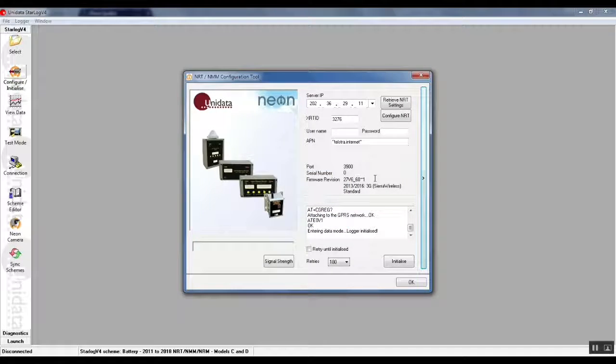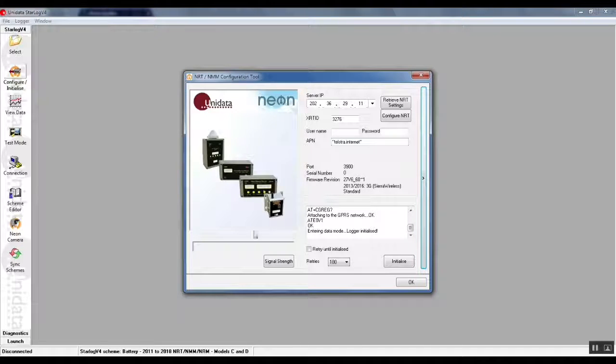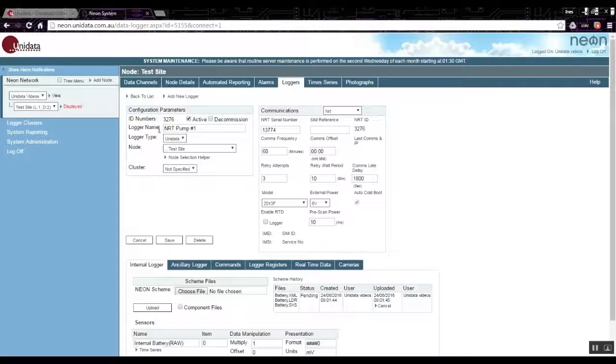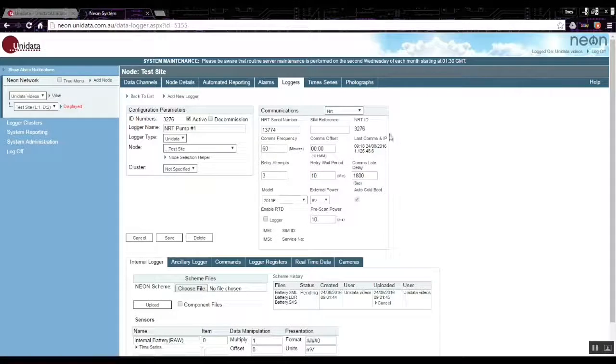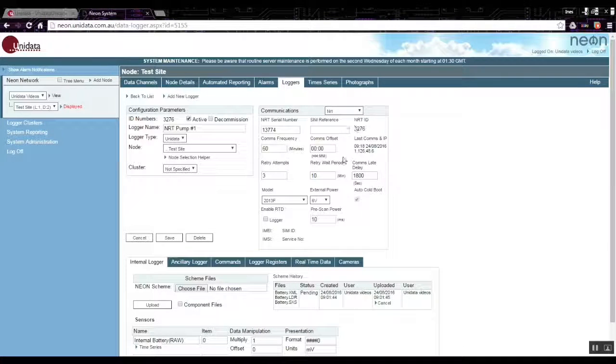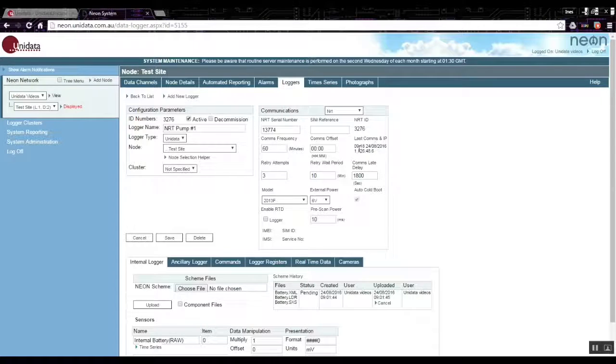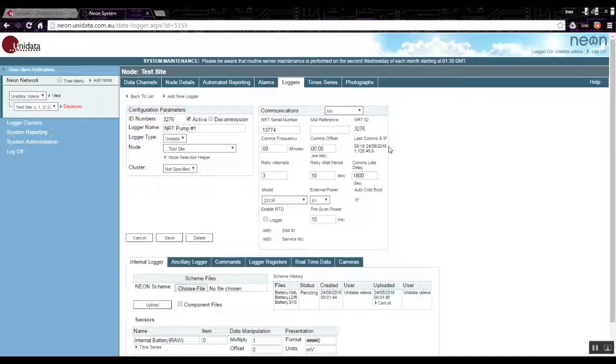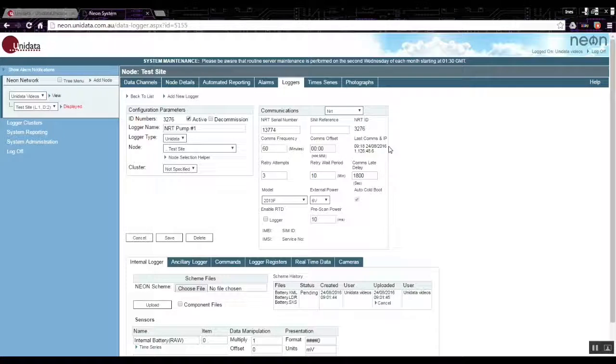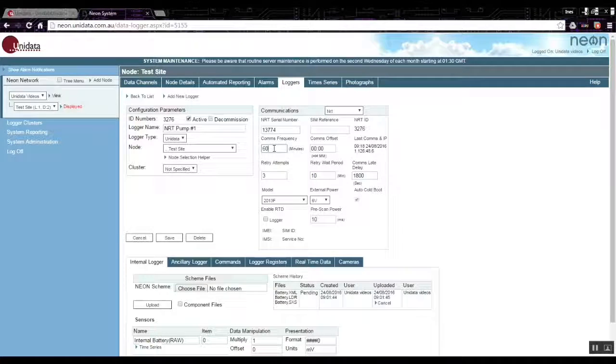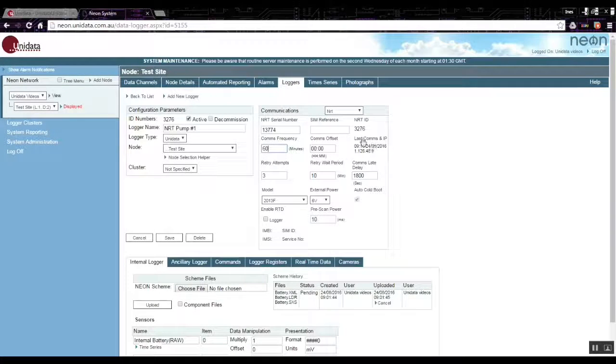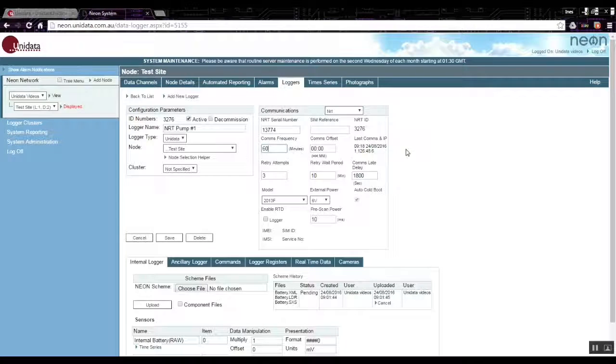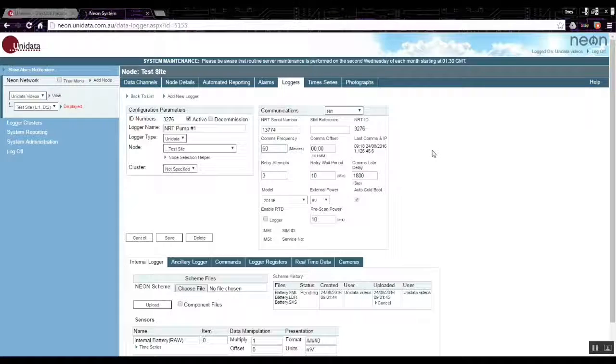We can go back to the neon server web page, refresh the page, and we now see on the right area over here that the last comms time has just been updated. That confirms that the logger connected to this particular node on the neon server. Each time the NRT communicates with the server, which will be every 60 minutes in this case, the last comms time gets updated. That's a confirmation that the NRT is still talking to the server and delivering data into the server.